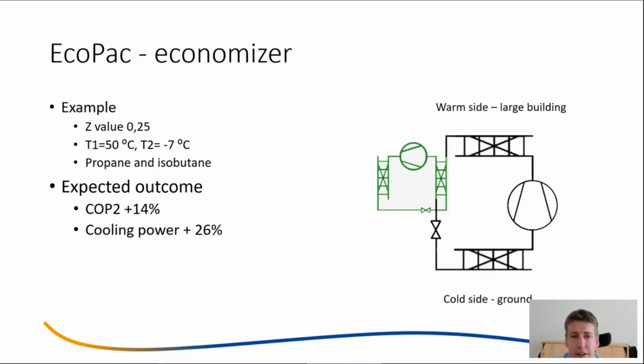If we look at the sizes here, we have a Z value, and the Z value in our case is the dimension of the two systems. So if the EcoPack is 1/4 of the larger heat pump, and we assume the larger heat pump is running at 50 degrees condensation temperature and -7 degrees evaporation temperature, and we have two refrigerants, propane in the larger one and isobutane in the smaller one, we expect the outcome will be a 14% increase in COP and a 26% increase in cooling power. You can see that the cooling power increase correlates to the Z value pretty well.